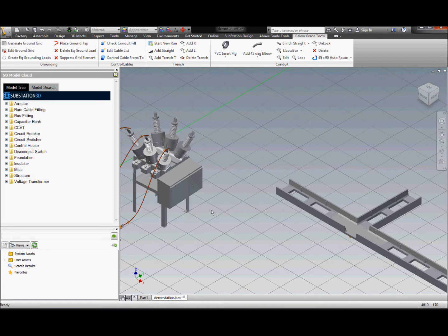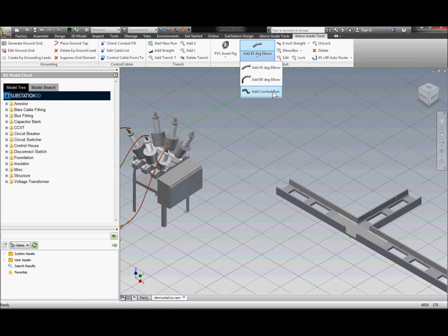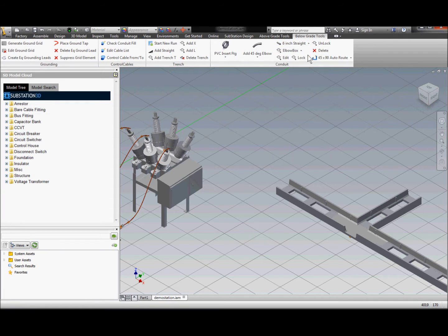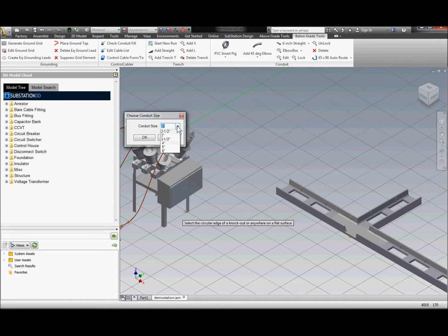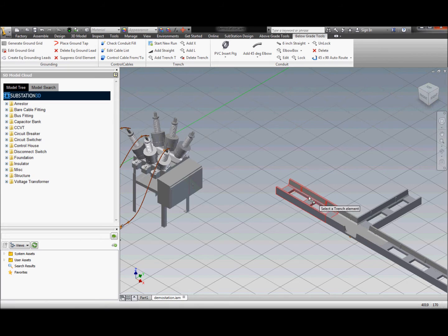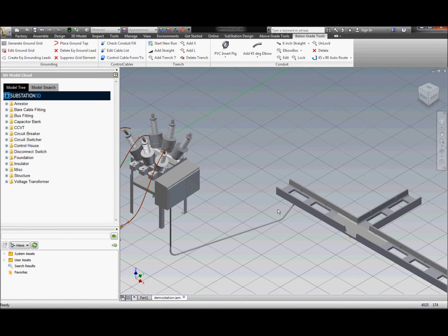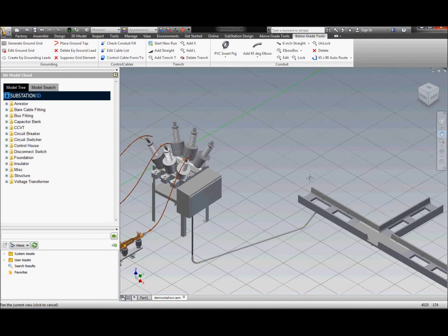We can build up a conduit run by starting with a PVC insert on the equipment, using elbows, conduit sizes and offsets, as well as different straight lengths and adjustments to build up the conduit run manually. We also have an auto-route feature that can end with a 90-degree bend or a 45. Let's pick this cabinet, pick the bottom face, pick a conduit size, and then pick the trench component we'd like to run to — and it's going to automatically generate a conduit run using individual parts, each made up and included in the bill of material completely. It runs that conduit down and automatically calculates the bend values.